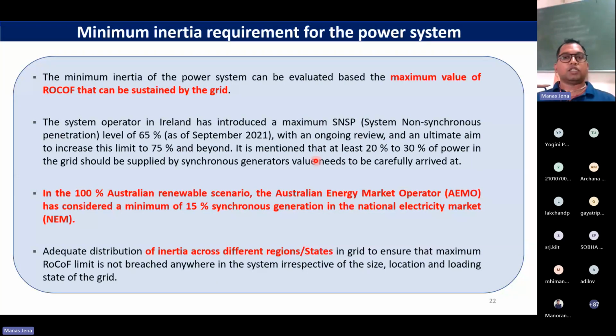It is mentioned that at least 20 to 30% of the power in the grid should be supplied by synchronous machines, as far as Ireland is concerned. What about Australia? In the 100% Australian renewable scenario, AEMO, their operator, has considered a minimum of 15% synchronous generation in their market.